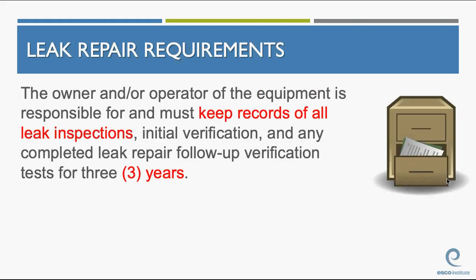The owner or operator of the equipment is responsible for and must keep all records of leak inspections, initial verifications, and any completed leak repair and follow-up verification tests for 3 years. EPA can come in and audit for 3 years.